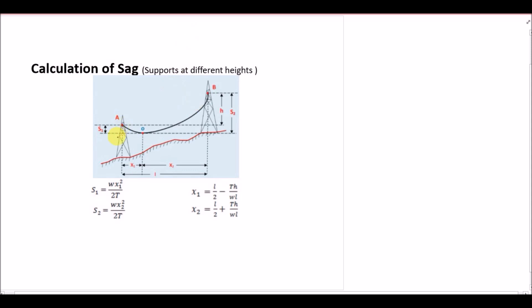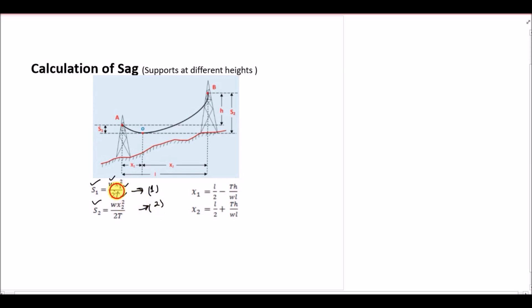We want to calculate the sag values, and I have already derived the generic formulas for sag s1 and s2, where w is the weight and x is the distance from the lowest point of the conductor to the support point under tension. I have written the generic formulas for both sags — s1 from tower A and s2 from tower B. We have two equations, equation 1 and equation 2, but we don't know the values of x1 and x2.